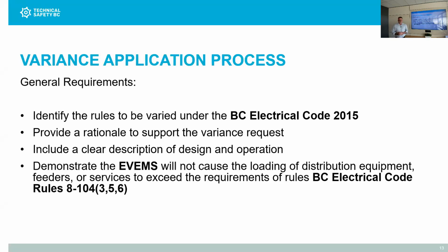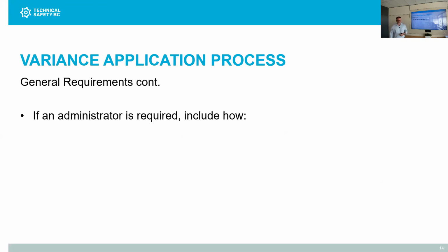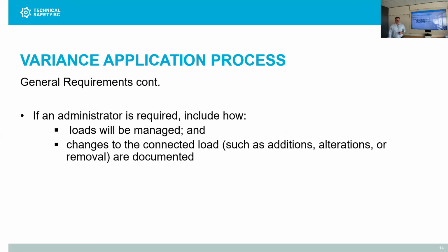And we're going to want to see a demonstration that the EVEMS will not cause the loading of any distribution equipment, feeders, or services to exceed the requirements of BC Electrical Code Rules 8-104, 356, which have to do with maximum circuit loading. Some of the additional general requirements we're going to want to look at: if an administrator is required, we're going to want to see an inclusion of how the loads will be managed and how changes to the connected load, such as any additions, alterations, or removal, are documented.